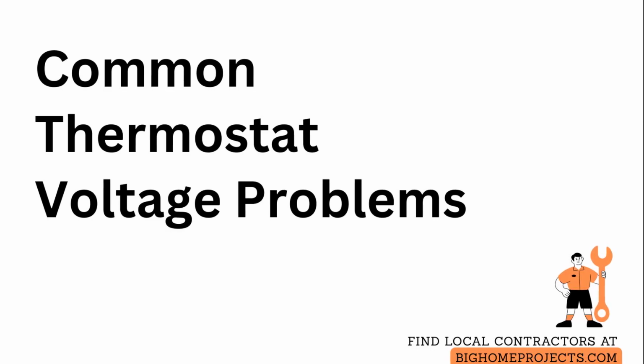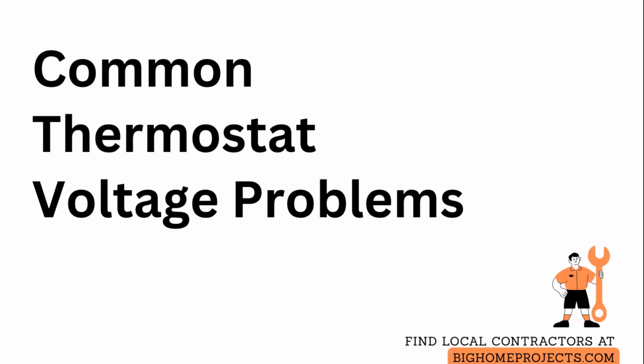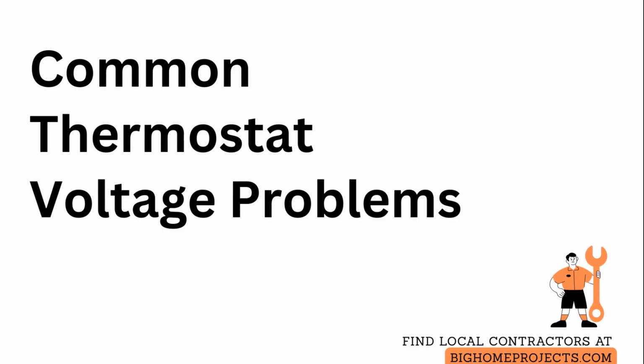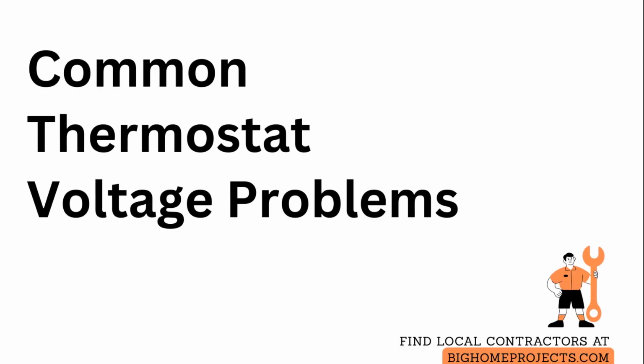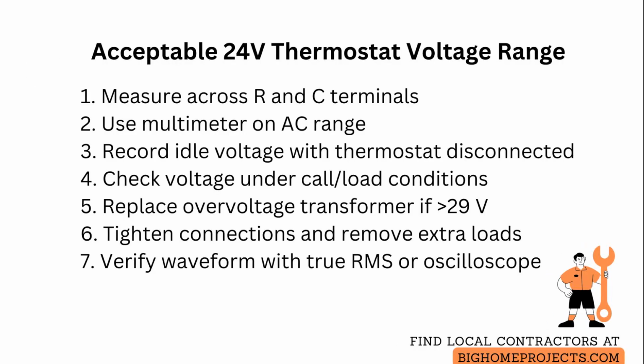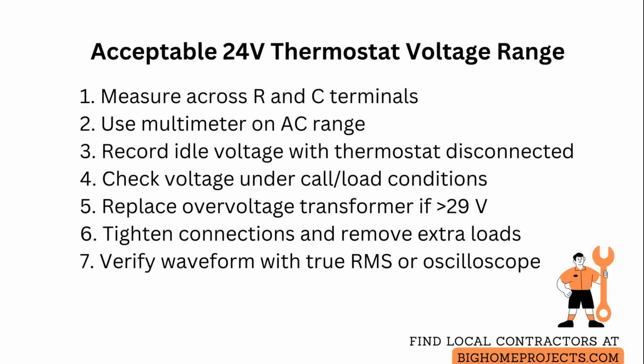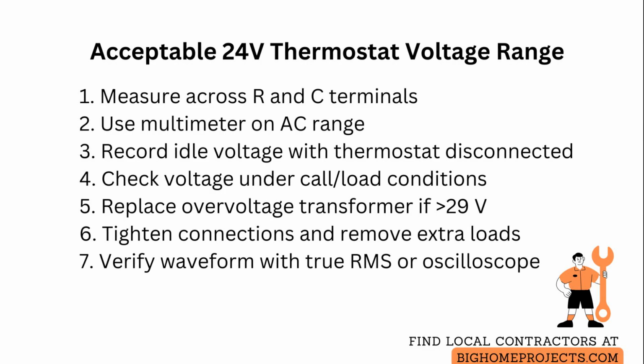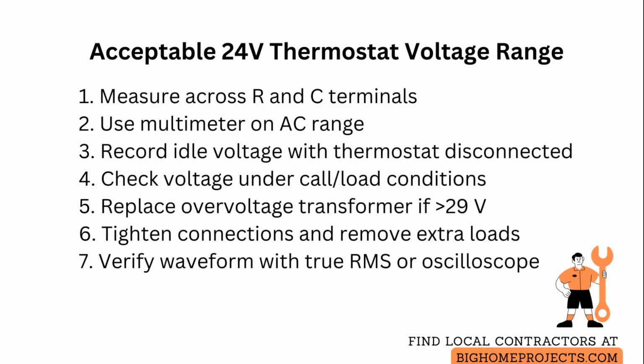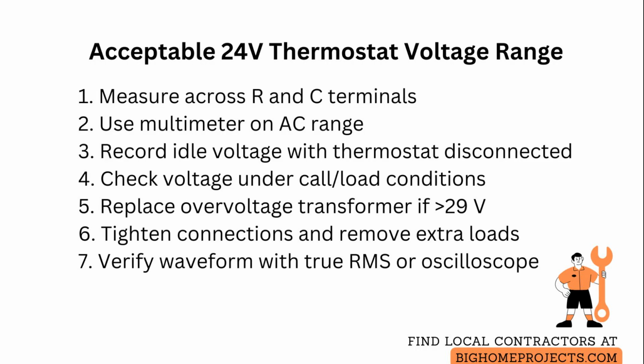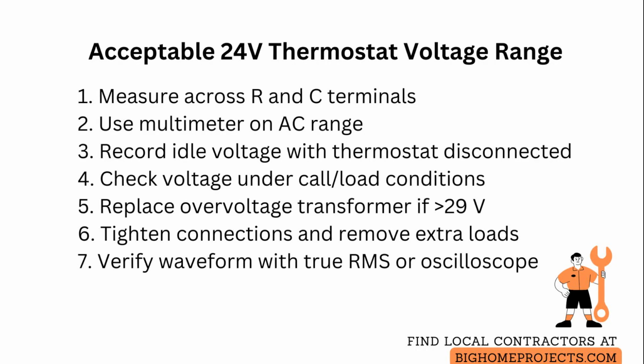24-volt control circuits in thermostats should read between 24 volts alternating current and 29 volts alternating current for normal operation. Thermostat systems using 24 volts alternating current rely on a step-down transformer to convert household voltage to a safe control voltage. Measure across the R and C terminals with a digital multimeter set to the alternating current range, and record the idle voltage with the thermostat disconnected and the system powered.